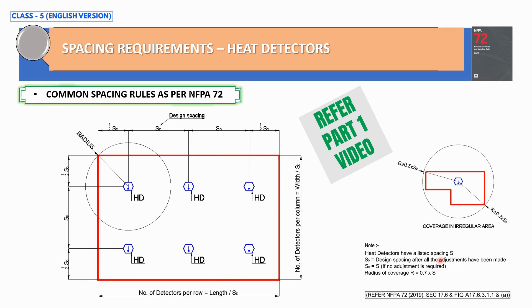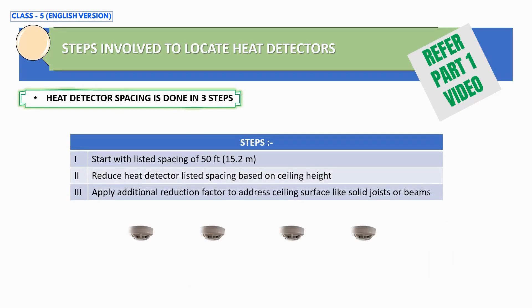Just for a thorough recap: heat detectors have a listed spacing of S, which equals 50 feet as per NFPA 72, and the design spacing between heat detectors is SD. The radius coverage for any heat detector is calculated using the formula 0.7 × S. The listed spacing is reduced if the ceiling height is more than 3 meters, and an additional reduction factor applies for solid joists or beams.